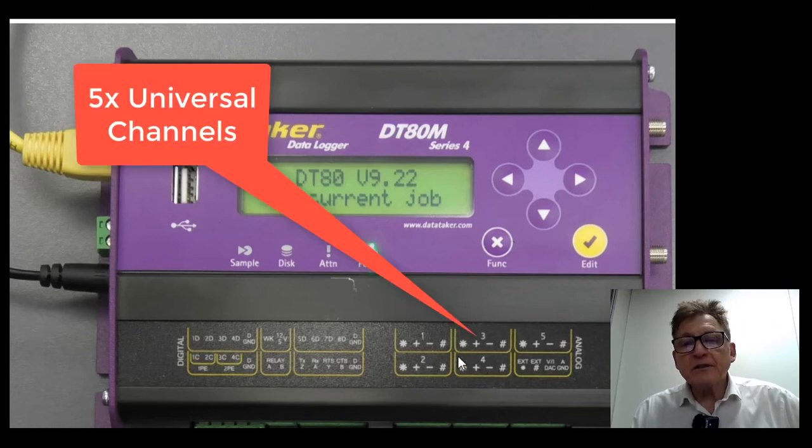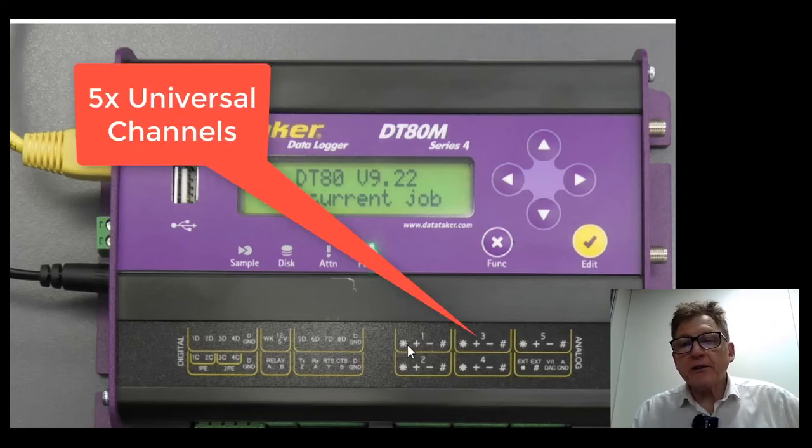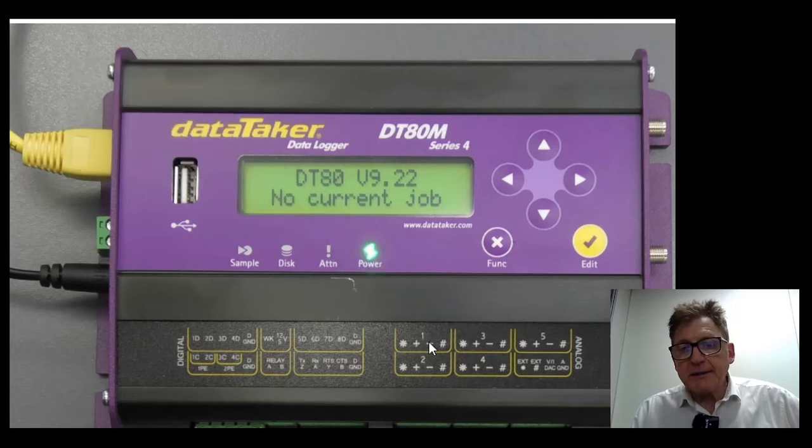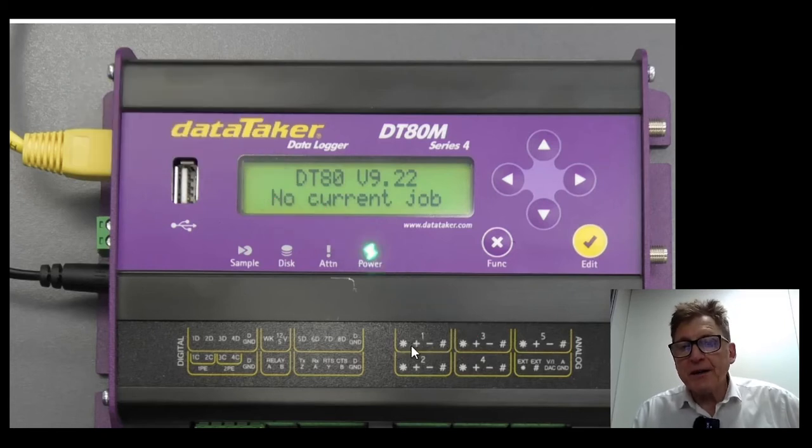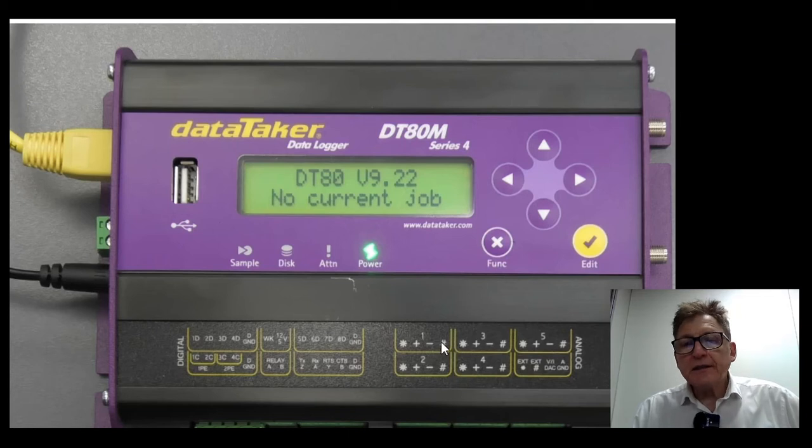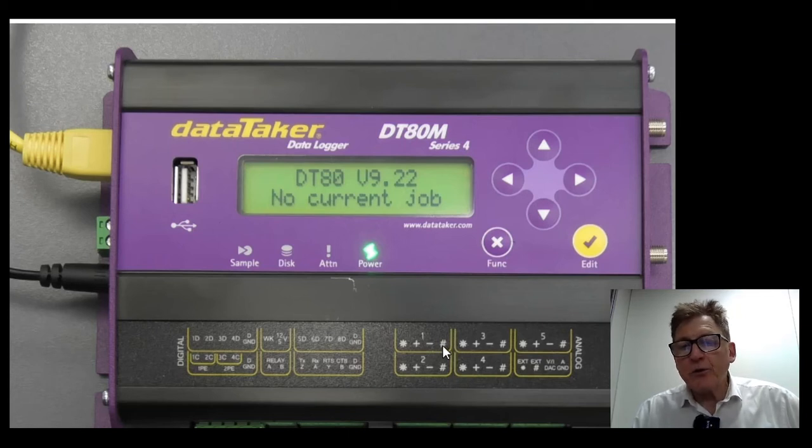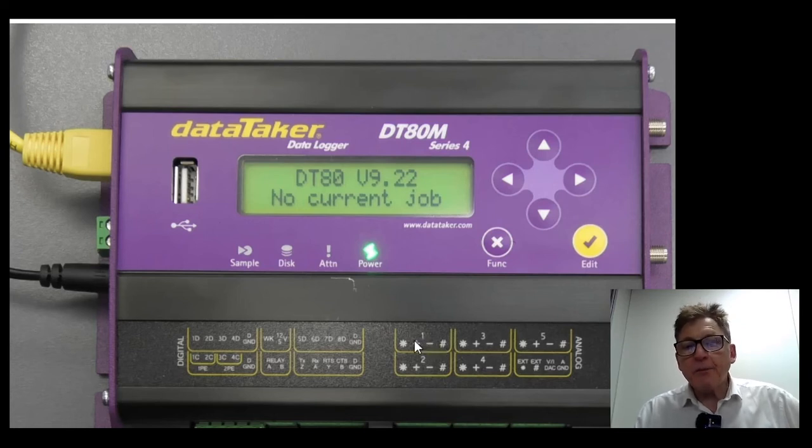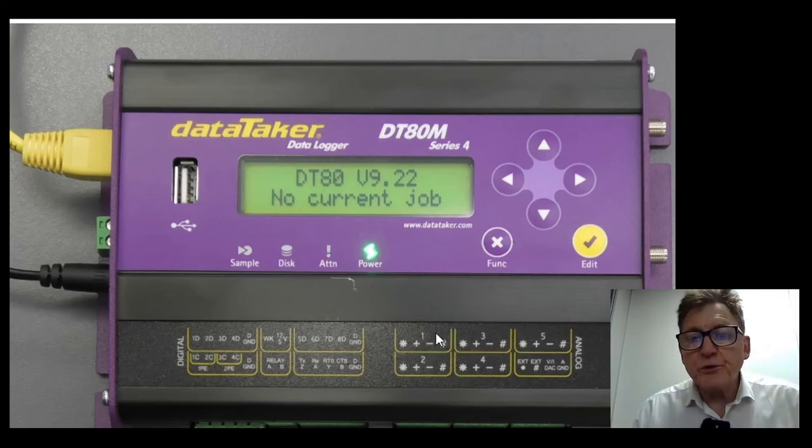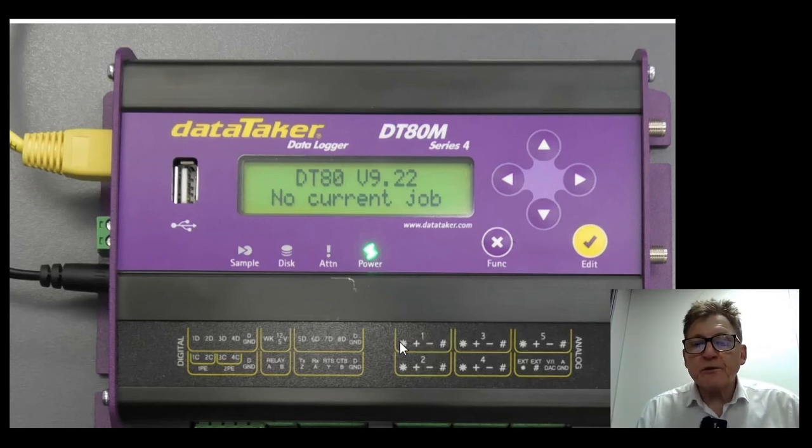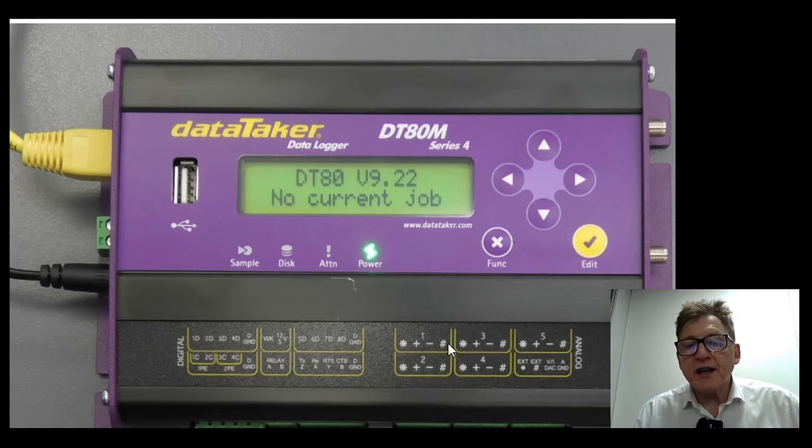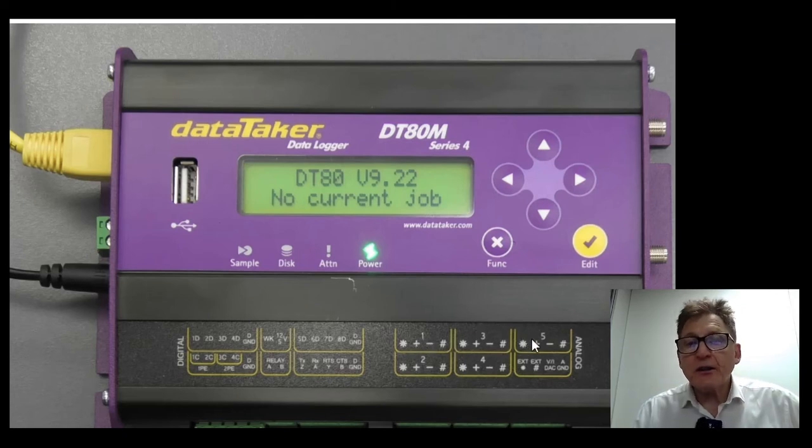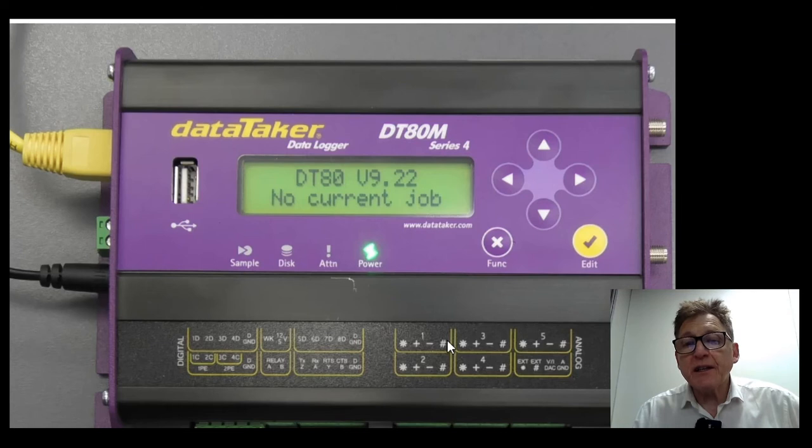Five channels. These channels are universal channels, so you can connect up to three inputs to a single channel. In other words, we have a common negative on that or isolated thermocouples. So you put two thermocouples, one between star and hash and the other one between plus and minus. So it gives you 10 channels or 15 if you have common negatives.